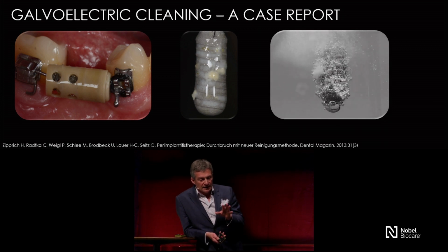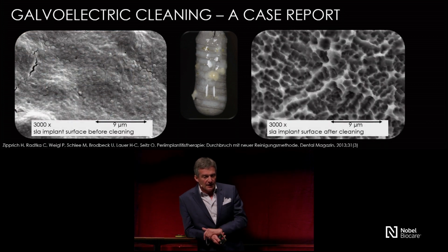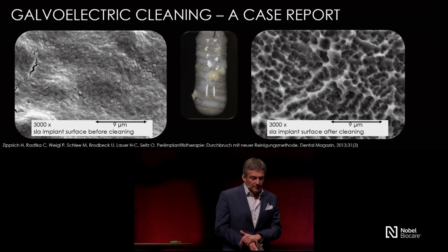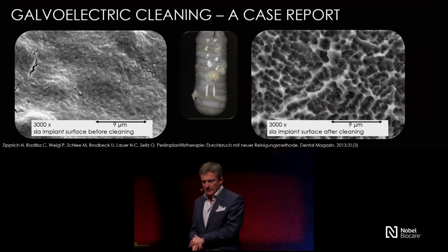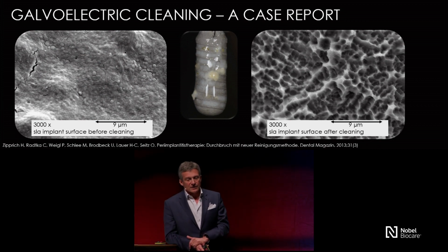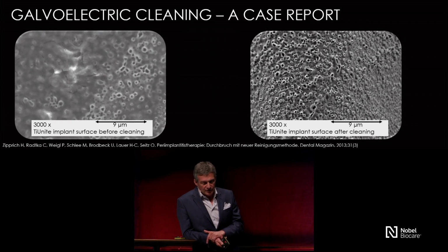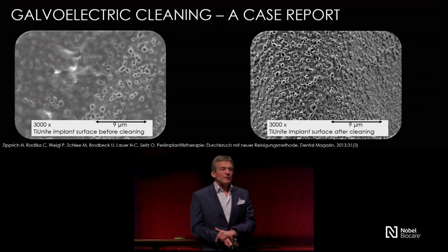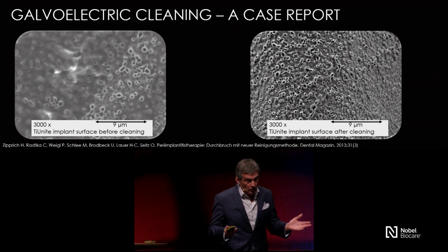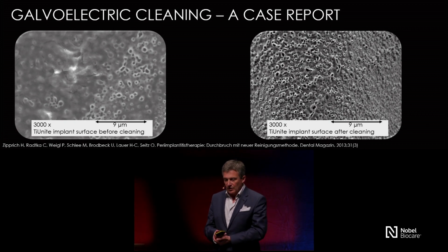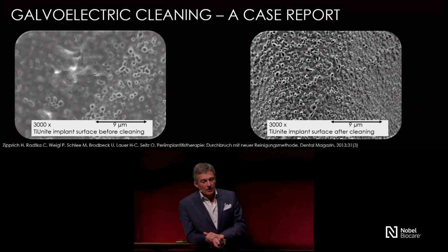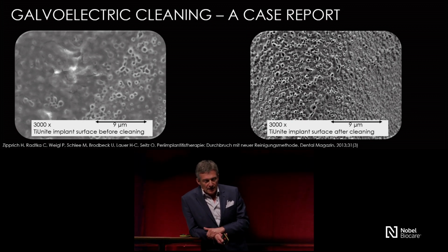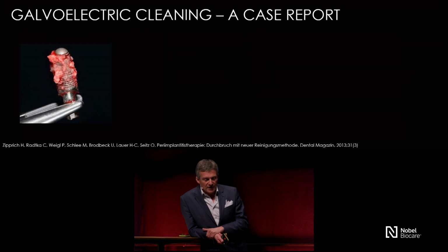And of course, we harvested some of those test implants, put it to the SEM before and after. And here you can see the biofilm after a few days. I think it was 8 days, I'm not quite sure to be honest. And after cleaning, this is a surface looking really like a fresh implant surface. Does it work only for a sandblasted and etched surface? No. We tested, as I said before, different surfaces, different brands, different kinds of alloys, and there was no difference found. We were able to remove the biofilm completely.